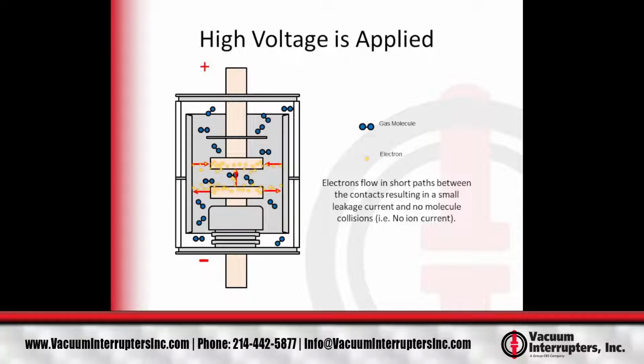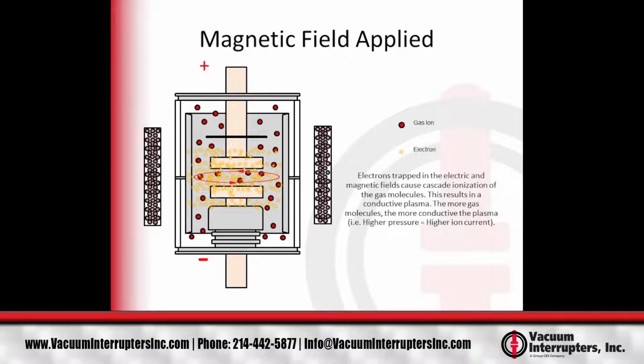For the MAC test, when we're actually doing this test, we apply a high voltage and we measure the normal leakage current of the bottle, just like you would for a DC high pot test. There's no real effect other than, again, a small leakage current across the vacuum interrupter from the electrons traveling between the contacts. Next slide, please. But if you apply a strong magnetic field while you're applying that high voltage, then those electrons become trapped in the magnetic field and they ionize all the gas molecules inside of the vacuum interrupter.